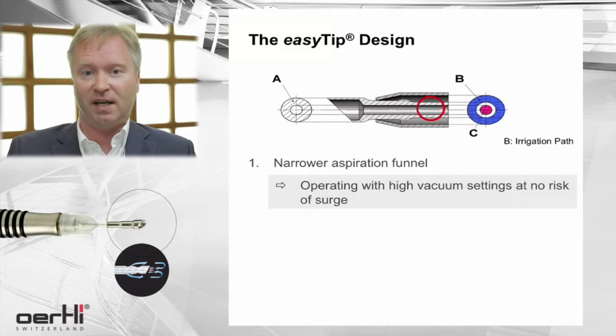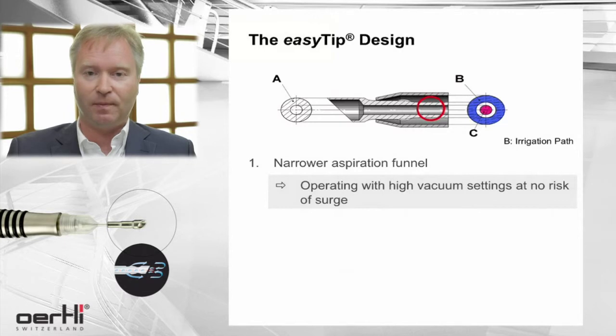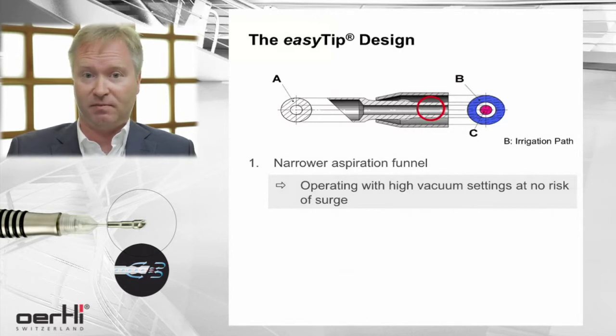You do not have to be afraid of surge at all. On the other hand, if you do have a narrower aspiration funnel, active aspiration is not affected by this. So you can apply very high vacuum settings.